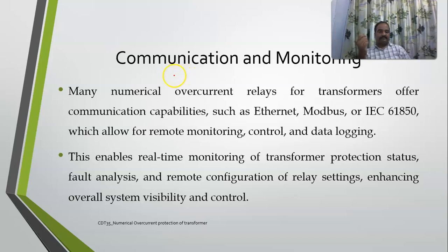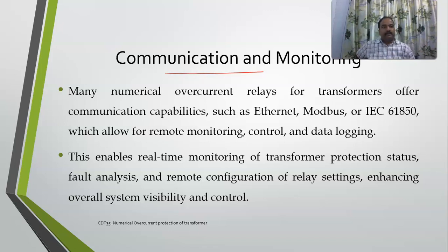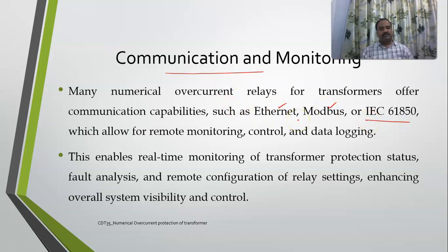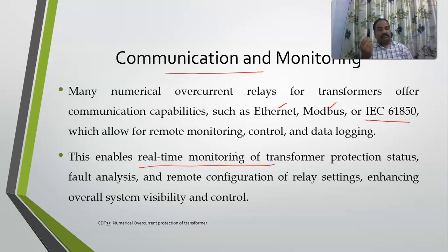The next consideration is communication and monitoring. Numerical relays must transmit data, so they must have communication capabilities. Various communication channels are available, such as Ethernet, Modbus, and IEC 61850. The relays must be able to communicate data, and real-time monitoring of transformer protection status, fault analysis, and remote configuration of relay settings must all be enabled.